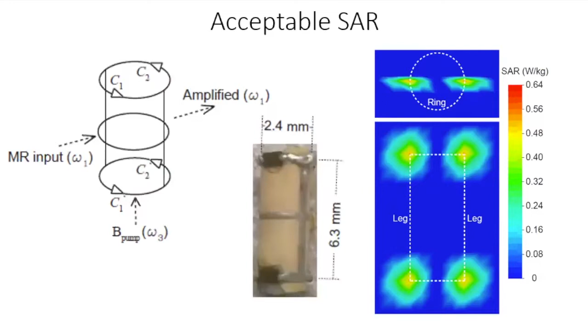So we did some SAR simulation in CST Studio, assuming that the required pumping power is about 0.6 dB lower than expected. And then we figured out that the detector has non-negligible SAR only around its end ring varactors. Even this non-negligible SAR is only 0.64 watt per kilogram, which is far below the average power dissipation limit set by the IEC. So this means that we can safely operate the detector, and we will only get about 0.61 millikelvin per second temperature rise. This is negligible. This is non-detectable by ordinary temperature probes.